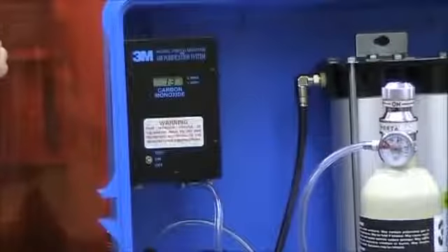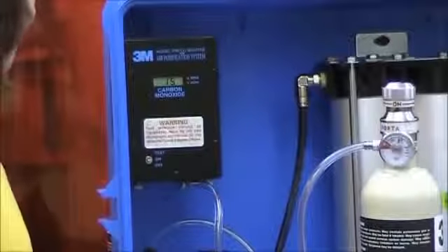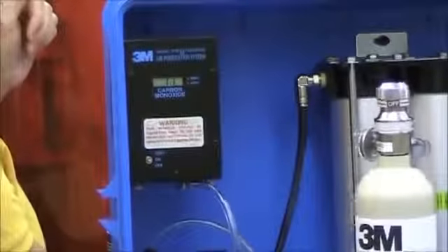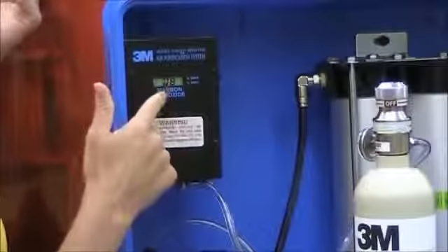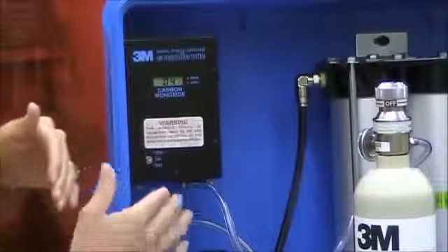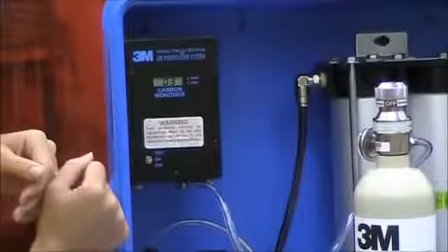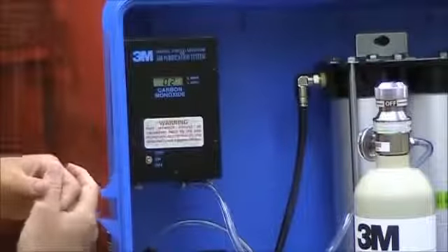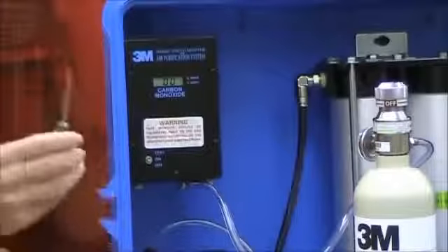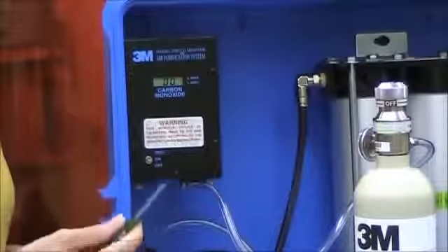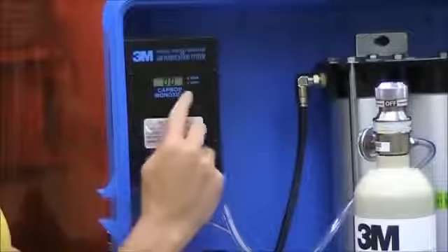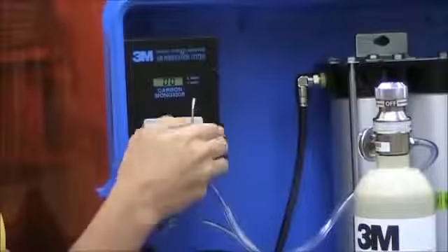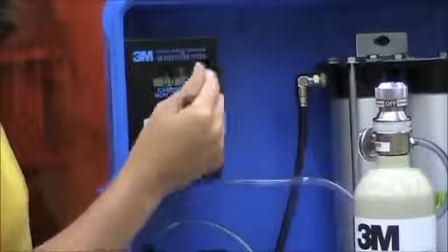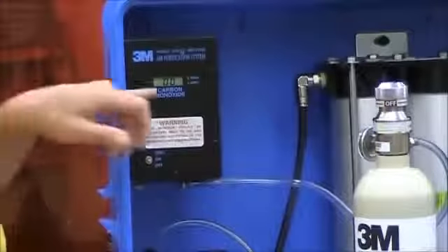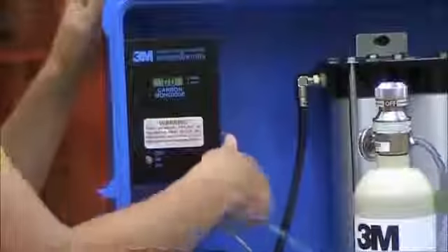So I've got the zero air flowing up to the monitor. Now the zero air is just that, we want it to read zero on the monitor. So mine went up a little bit at first. It's coming back down to zero. It's at 3 and 2 parts per million. If I need to adjust it, you'll use the small screwdriver that came with the calibration kit. And for the zero air, you would adjust the zero potentiometer either counterclockwise to lower or clockwise to raise the reading on the screen. Mine is here at 0, so I'm good for that.